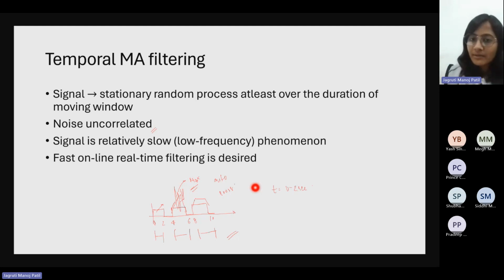With that acquire, it will show you whether the signal can be acquired in sample mode or in average mode, and if you're acquiring in average mode, how many realizations of it you want. If you increase the number of realizations, it's ensemble averaging. But if the number of averages is the same and you increase the time duration, it's the temporal moving averaging filter, because the reference or the timeline is always the same over there.